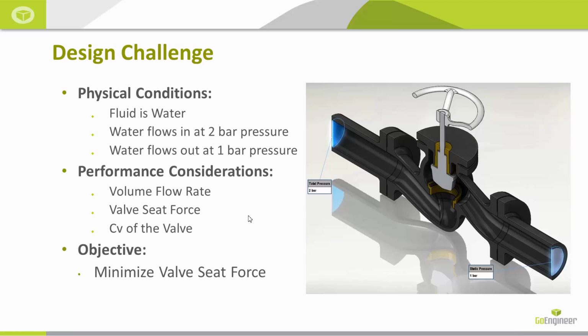We're also curious what the force is on the valve seat in the middle here. Then, using all this data, we want to look at the valve coefficient per those analytical equations that we showed in the beginning. An objective, as we go towards the end, is to come up with a design that minimizes the valve seat force.